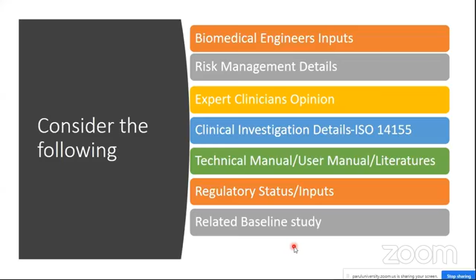And definitely you can have risk management details. You can see the risk management reports of other predicate devices, or publicly available literature. All those things will give some hint on how this device will behave. And definitely an expert clinician's opinion is very important. You also need to check the clinical investigation details published as per ISO 14155, and the technical manuals and user manuals. Sometimes it will be listed in the user manuals or technical manuals, then other literature, regulatory status inputs, and related baseline studies, if any were conducted. You can have a look at all those things for more inputs.